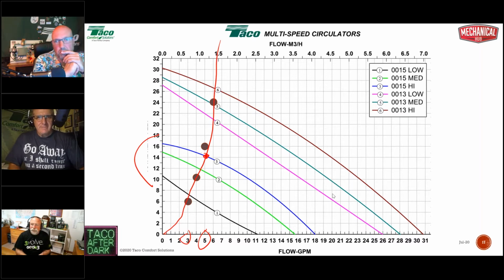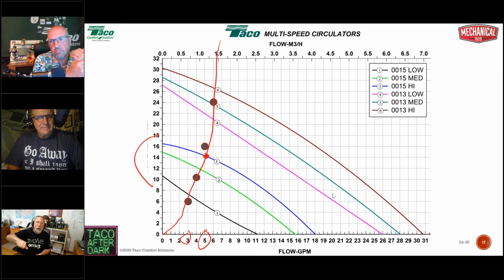Take that with kid gloves, but that is the time, once you get everything up and going, everything's purged, everything's full, everything's doing what it's supposed to do, and you're doing the commissioning of that, that's a good time to look at those two temperatures. Look at your delta T and turn the pump down. We always want to run a pump on high speed for a short period of time to burp the air out of it. It's a wet rotor, but then always turn it down.